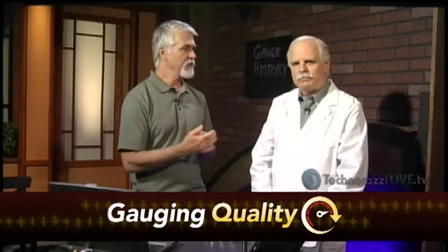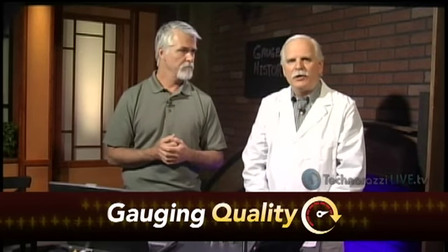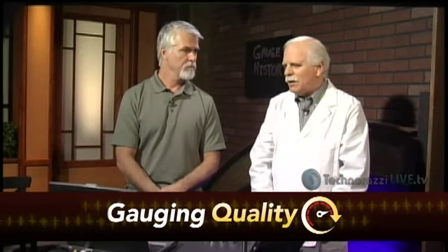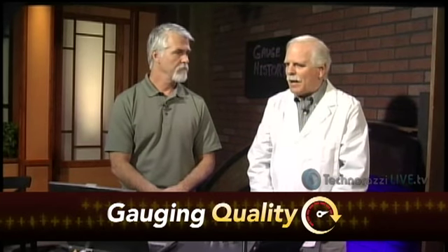So let's step through some of the things you said that we could actually glean from a history. All right. The first thing we'll look at is the performance of a tool over time. The history is going to show its wear. It'll show how often adjustment was needed, how stable the tool is, how linear the tool is, how it tracks along its paces. All this information is available. You already have it in the history as you've typed it in, as you've kept your records. This is a quick way of getting to it. It's so much easier when you can see a graph already made. And like we said, in the older days, we had to do it all manually.